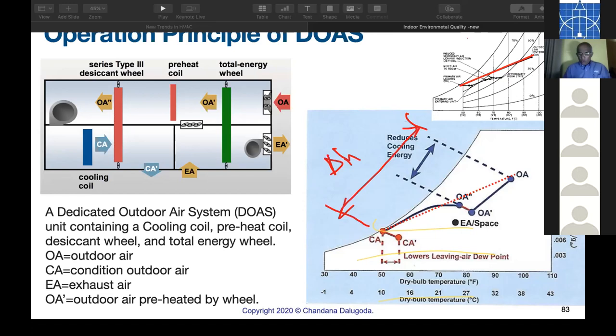So you have entering air going through the total energy wheel, goes through a desiccant wheel and comes back with the cooling coil, cooling and dehumidification, and then chemical dehumidification here, ending up here. So outdoor air now leaves here and massive heat, energy saving, OA to OA dash.